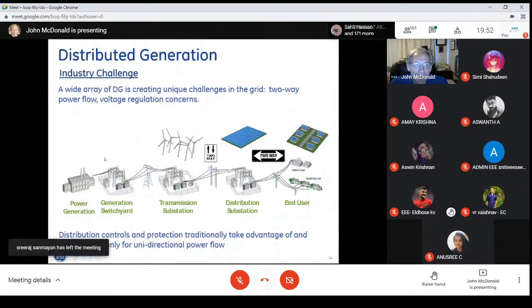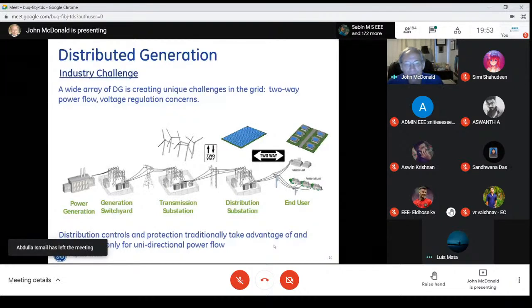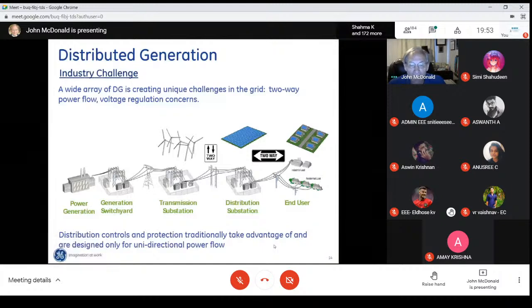So let's look at microgrids and distributed generation. One of the things with the distribution part of the grid that I say at the bottom of the slide is we designed controls and protection for the distribution part of the grid to take advantage of electricity flowing in one direction, which was the case for many years. The distribution part of the grid had electricity flowing from source to load only. So if you work for a utility and you were going to go out in the field and do maintenance, you knew that if you opened the upstream device, you always had a safe working condition because electricity flowed in one direction. You open up the upstream device and you de-energize the rest of the feeder, right? Well, that's not the case anymore, right?